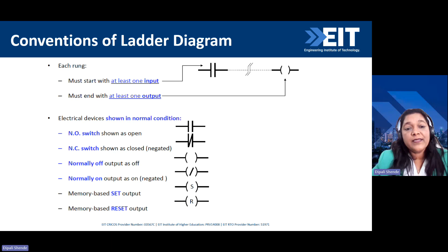So these are the conventions of a ladder diagram, and these are some examples. If you want to use the same output somewhere, we can use the same name or labeling, like start, stop, run - we are using the run button here. A device can appear in more than one rung of a ladder. For example, if an output's value is needed as an input elsewhere, use the same letters or numbers to label the device in each situation. That is the basic concept: we use the same number so it's understood that we are using this output as an input here.